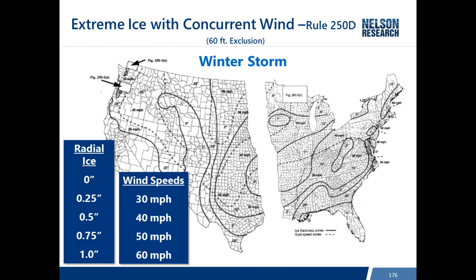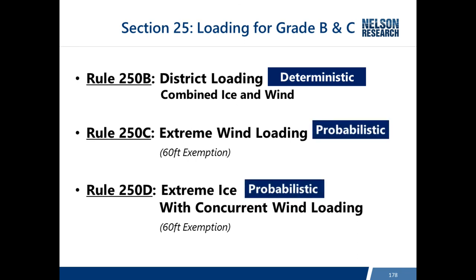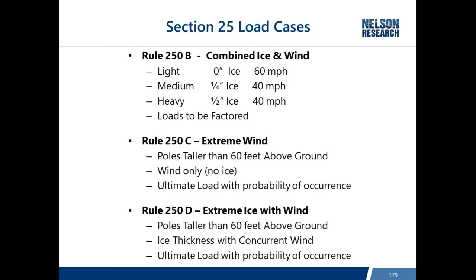Looking at all three load cases: Rule 250B is deterministic and loads must be factored, whereas Rules 250C and 250D use weather-data-based maps with a known probability of occurrence and use ultimate loads that are not factored. Rules 250C and 250D are only required to be applied to poles more than 60 feet above ground.